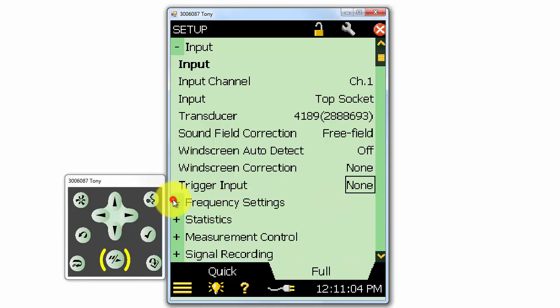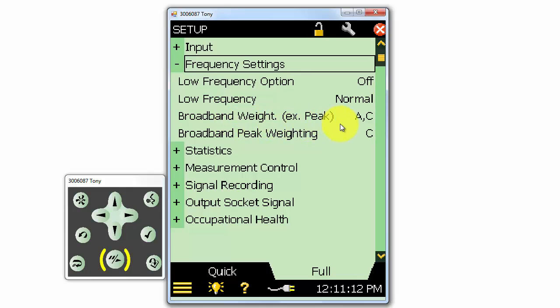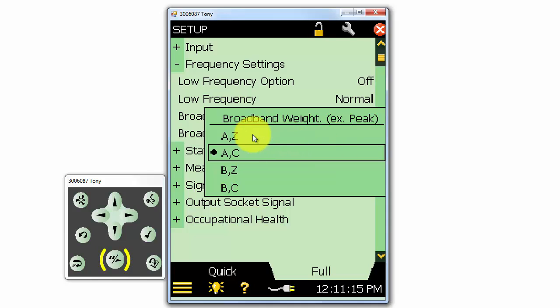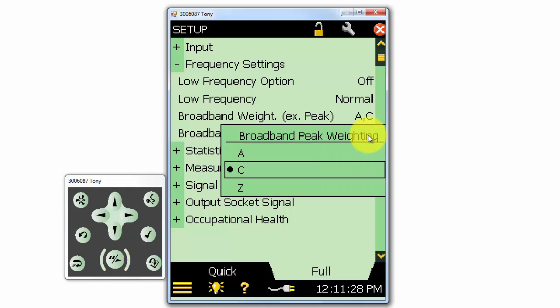Next, we can select the frequency settings for the measurement. We can select two weightings to be measured at once for the broadband or overall RMS values. We can select A and Z, A and C, B and Z, or B and C to be measured at the same time. The broadband peak detector can have its own frequency weighting, but only one can be used at a time for a measurement. The default weighting is the C weighting, which is common for impulsive noise testing, but we could also select an A or Z weighting instead.